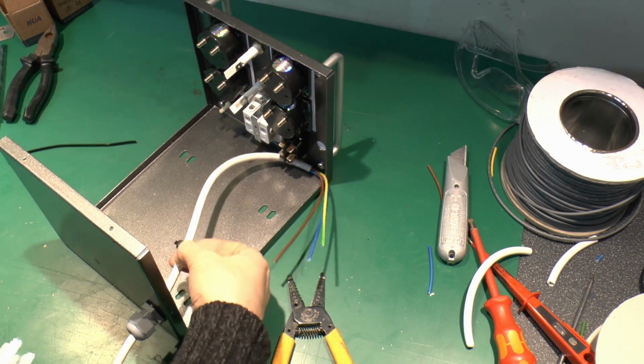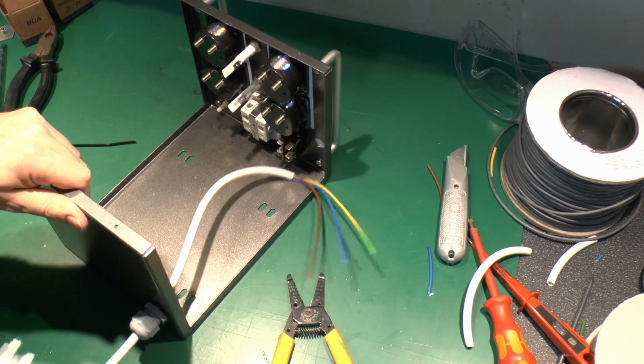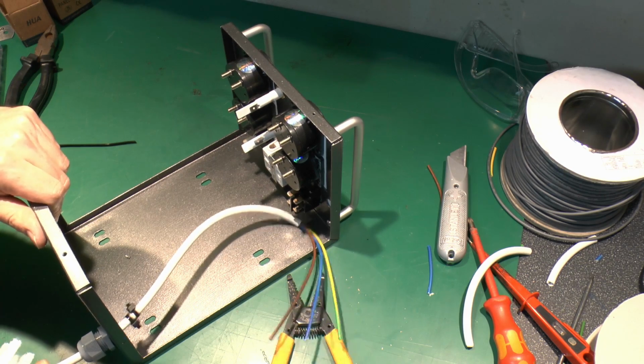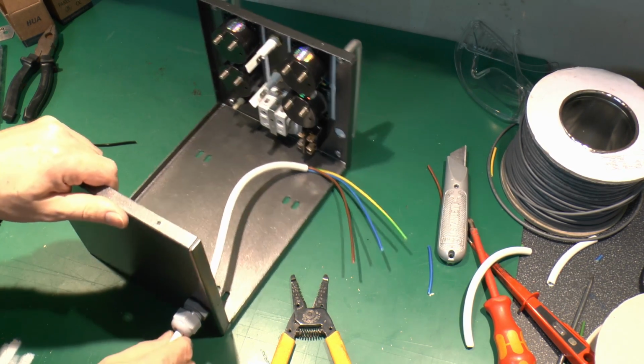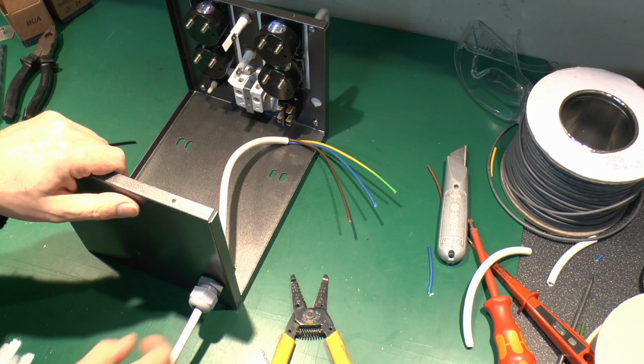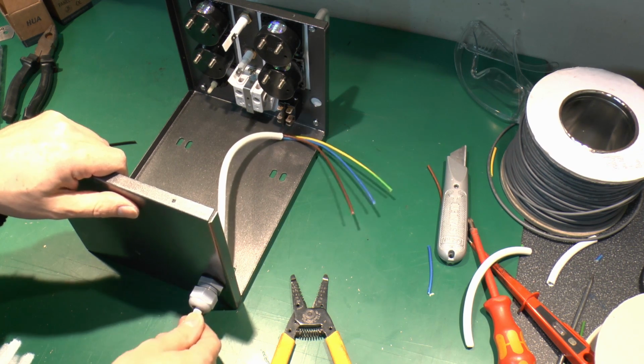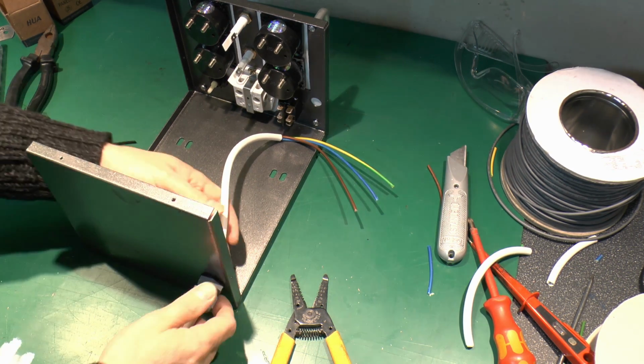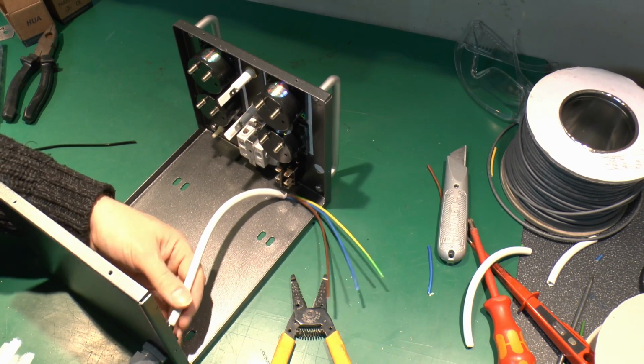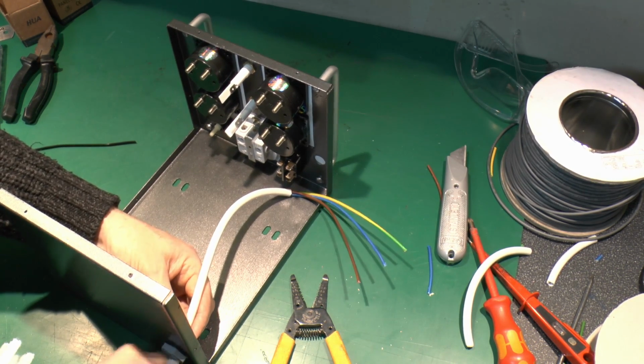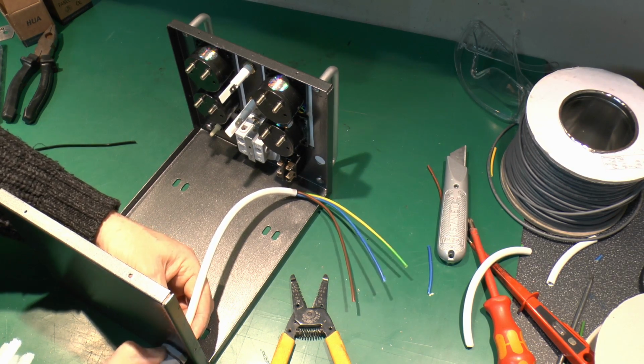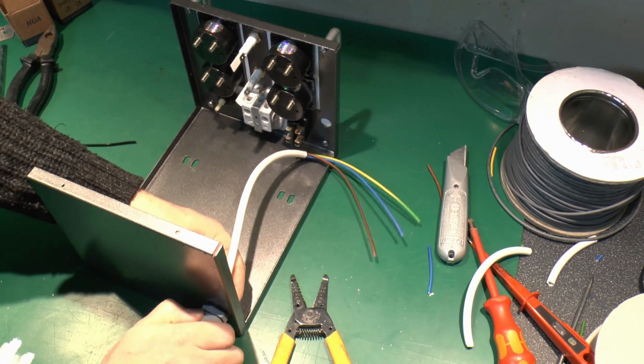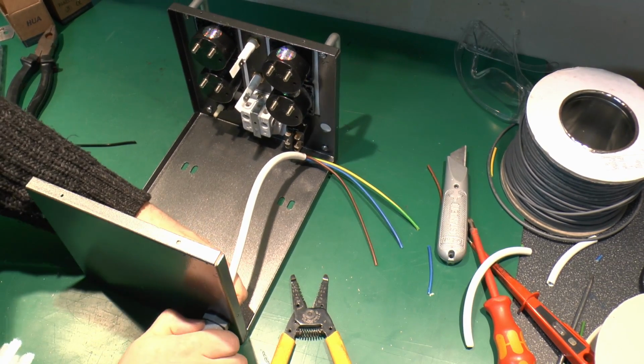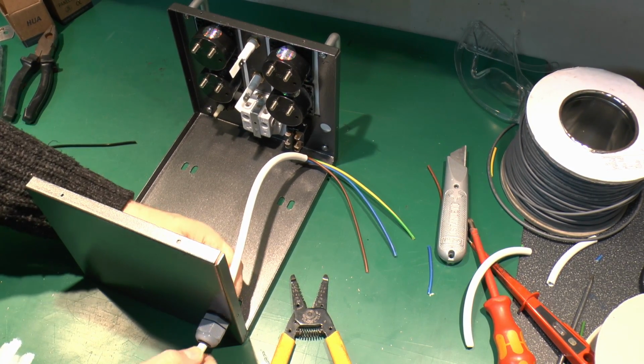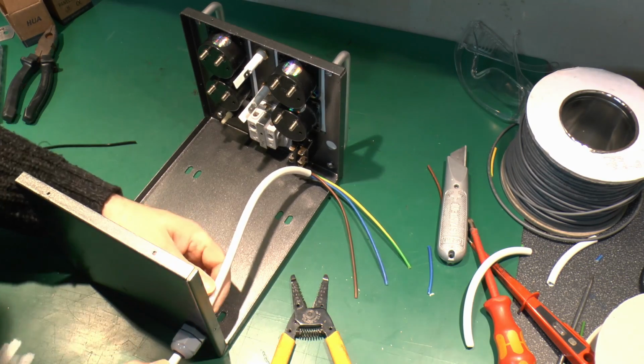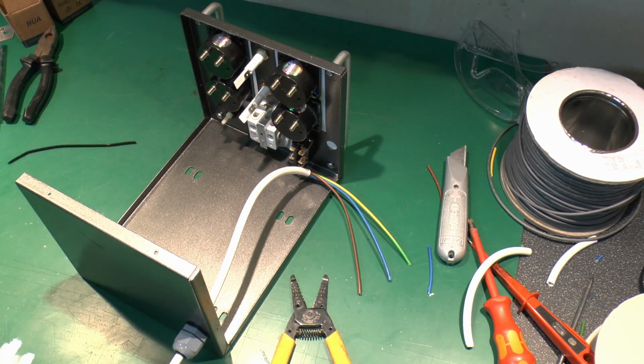The reason for these is that they grip on the cable and stop it pulling through - see, that will stop it going through there. This fitting on its own is just a rubber seal, and that will grip on the cable, but they don't grip all that well, so over time it could gradually creep out of the equipment. With these things they'll prevent that from happening, so it's generally a much better idea to have that on the inside, and then this will just seal down to prevent dust and whatever getting in. We'll tighten that down to a reasonable extent - I've already tightened the fitting, so that's now secured in there.